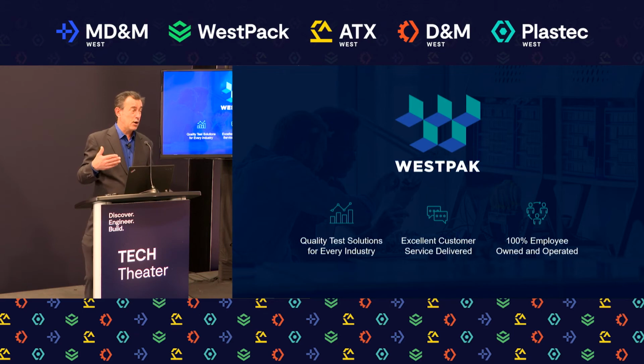That's actually the low end of what we have to offer. We have plus 50 degrees C, plus 55, and plus 60, because those are the most popular. Even at plus 50, you're going to have a longer time in the chamber, so why not bump it up to 55 degrees C? But then with that humidity component, you have to ask, do I really want to go to 55%? That's going to be huge. Maybe I keep it at 45%, something like that. So it gives you a range, and it's not defining it. That's the key. It's up to you to define that.